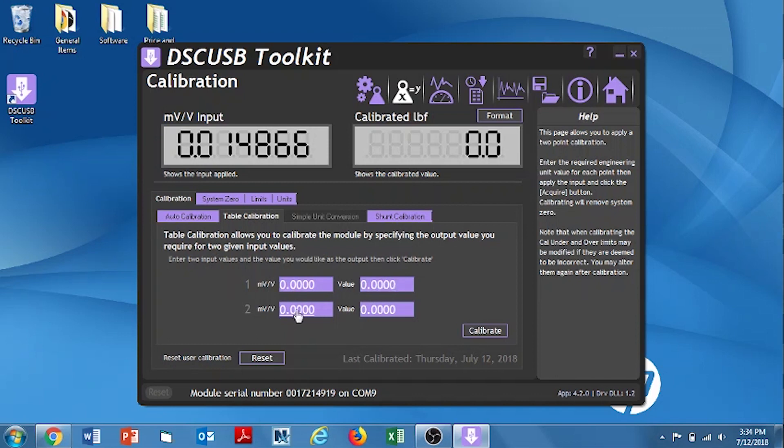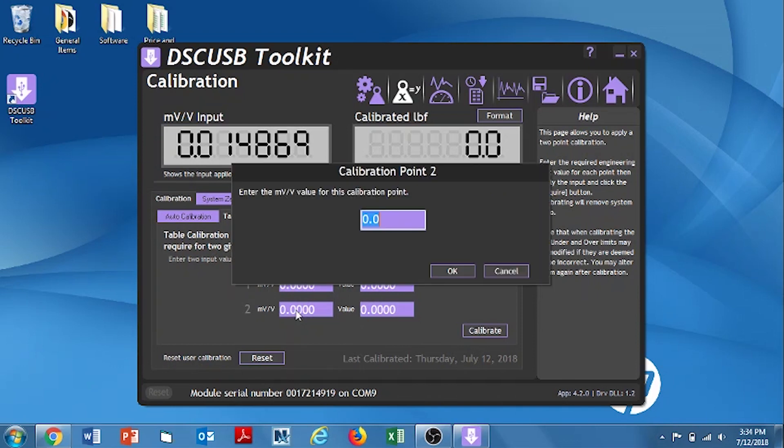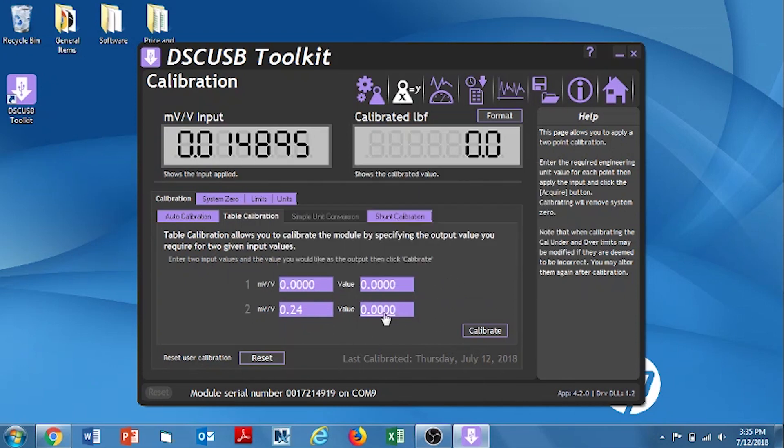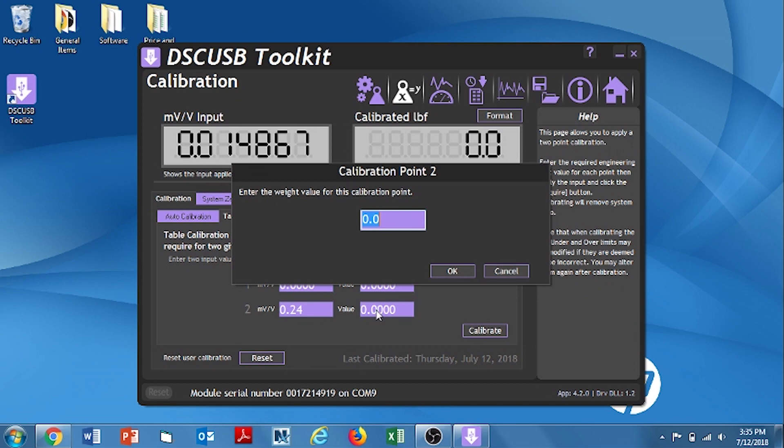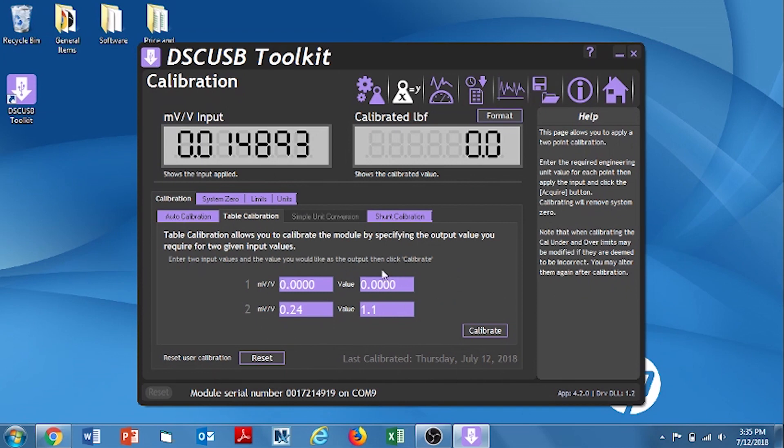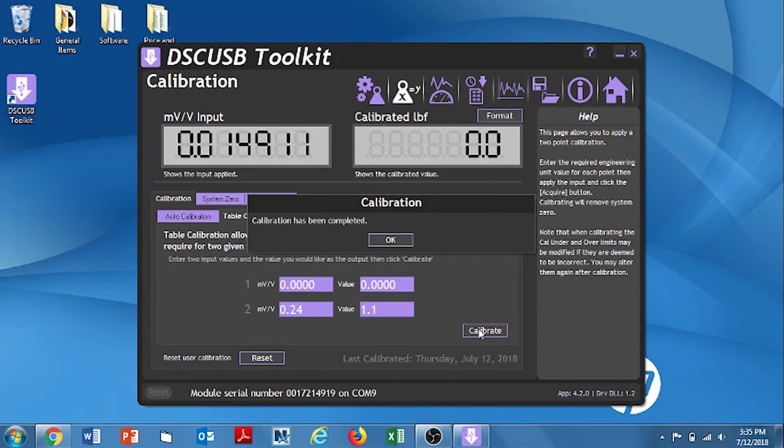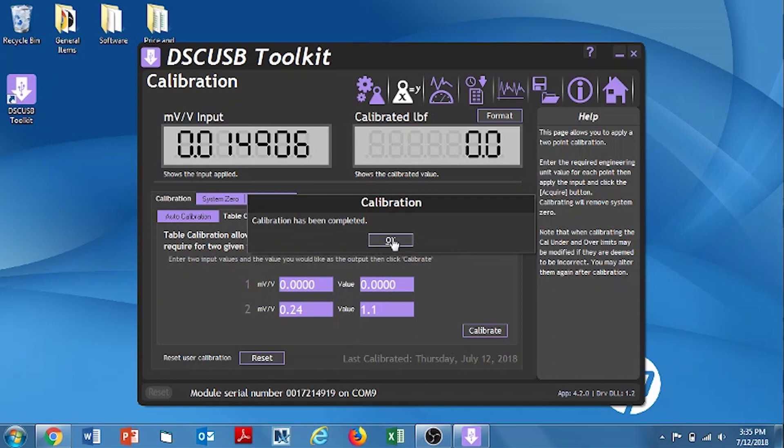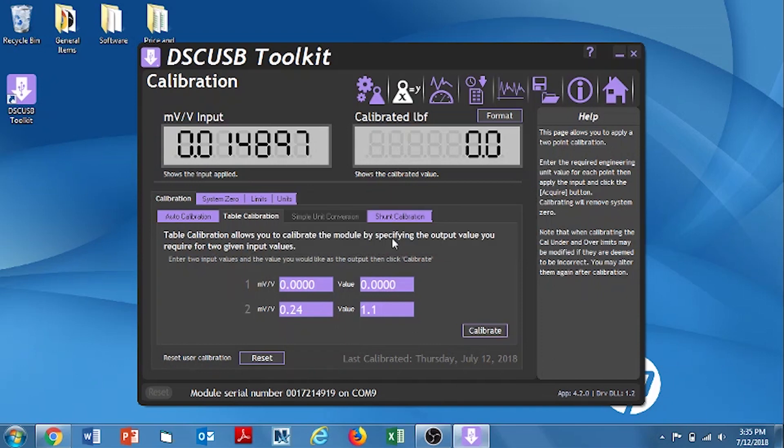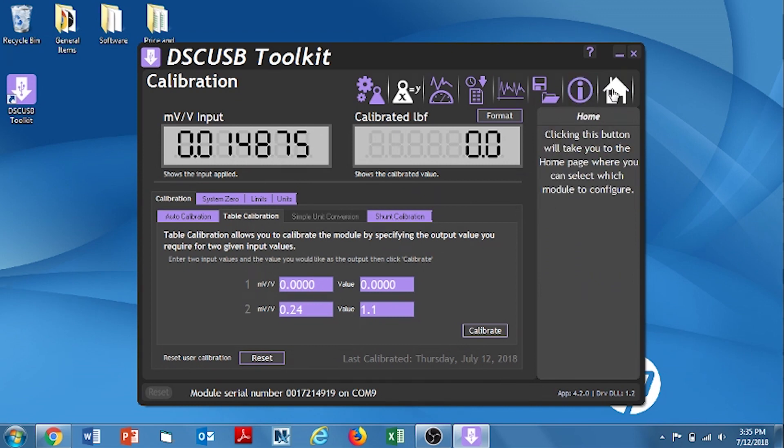For our second point, this will be the value that's on our cert. So for our calibration test, this will equal zero point two four. So that's zero point two four millivolts per volt. And that equals one point one pounds. I'm typing those values in and hitting OK. And as you can see, all the values are displayed. We double check and make sure they're correct. And all we do now is hit calibrate. It says calibration has been complete. Click OK.